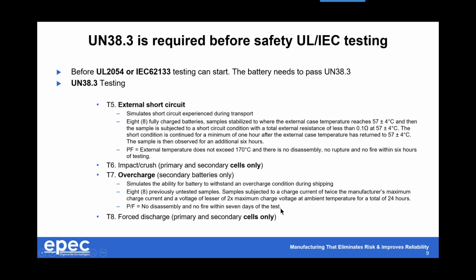But one thing you'll notice on T7 is they don't have the open circuit voltage requirement like a lot of these other tests, where it has to be 90%, what have you. They expect permanent failure of the battery pack under these conditions. And sure enough, very few of them do survive it. Some of our electronic safeties have no problem. They reset and life is good. And the pack, you could actually reuse it after T7 with the more sophisticated medical safeties that we put on these batteries. But for the simple devices, yeah, you won't get a working battery after that test.